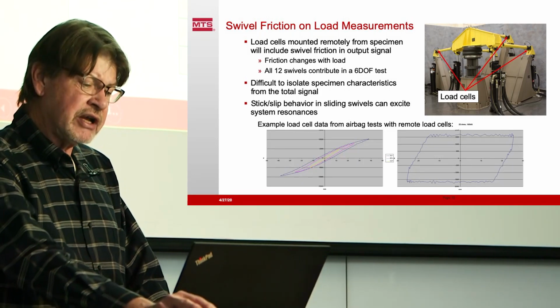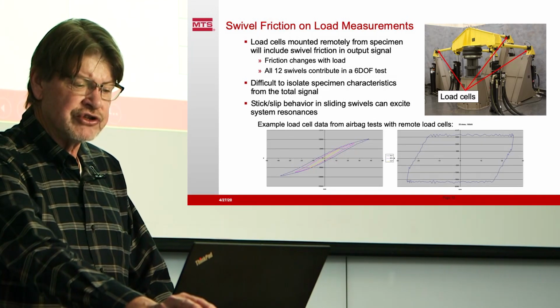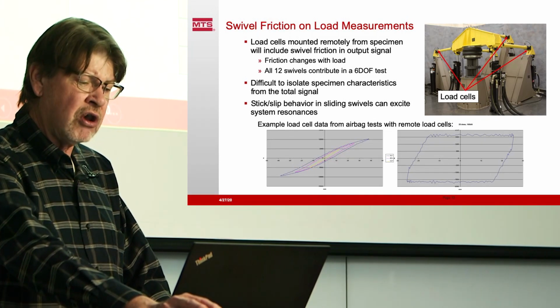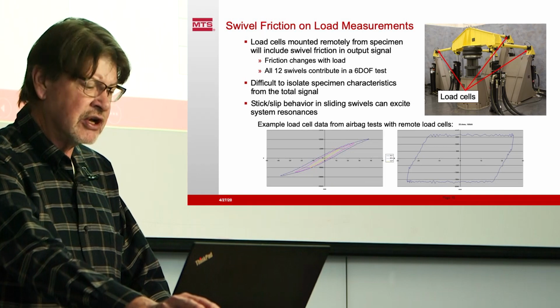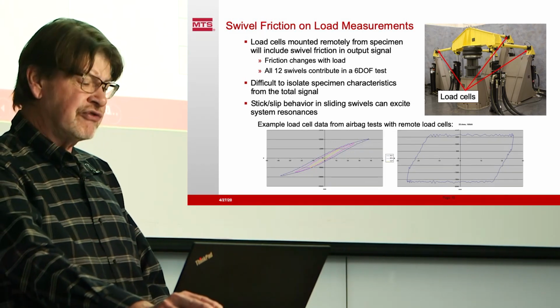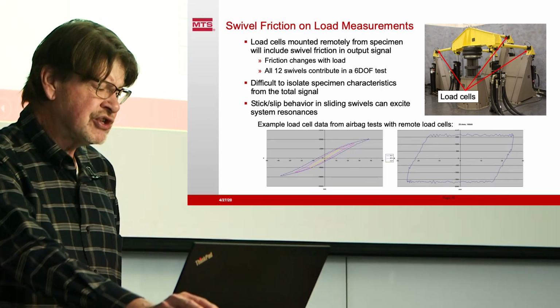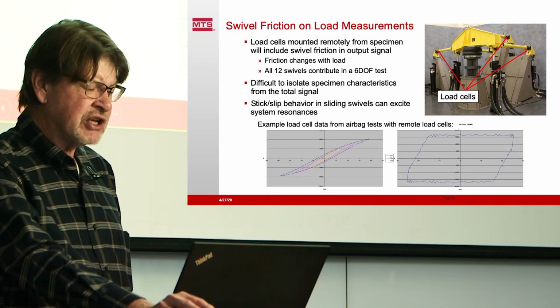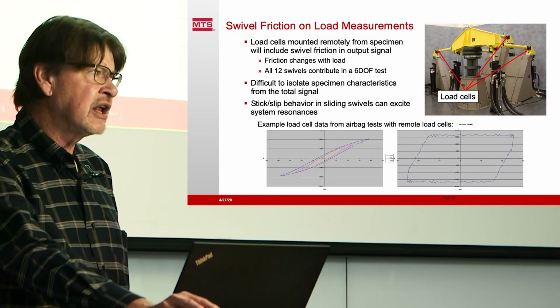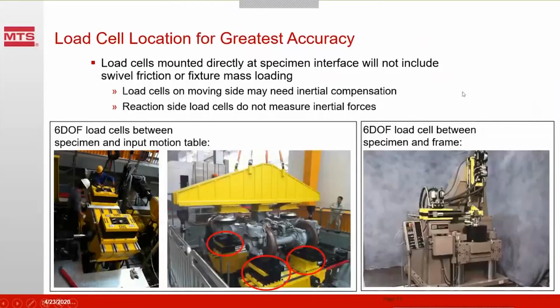Well, every bearing has to move when we move, so every load cell is going to pick up the friction from all of the swivels inboard of the load cells. That's a very common source of error. The other thing we can run into is stick-slip behavior between the sliding swivels, which can excite system resonances and add a lot of noise on the system.